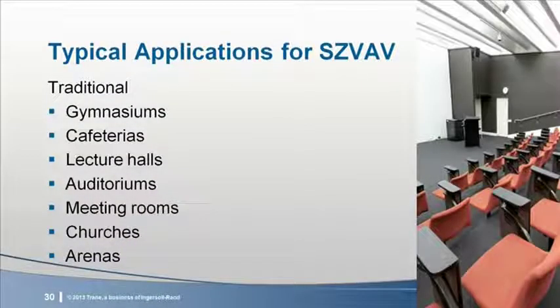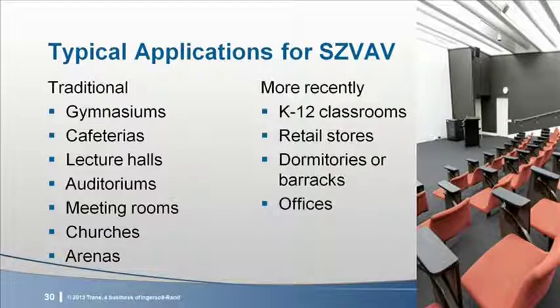Single-zone VAV is not a new concept, but due to the aforementioned requirements in energy codes and an overall heightened attention to reducing energy use, we're seeing it used more and more. Traditionally, single-zone VAV has been used for larger, densely occupied zones that have variable cooling loads. Common examples include gymnasiums, cafeterias, lecture halls, auditoriums, or large meeting rooms, churches, and arenas. However, because of increased focus on reducing energy, we're also starting to see these systems used more in K-12 classrooms, retail stores, dormitories, and even offices.